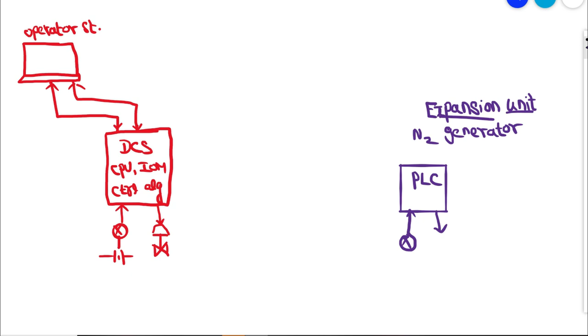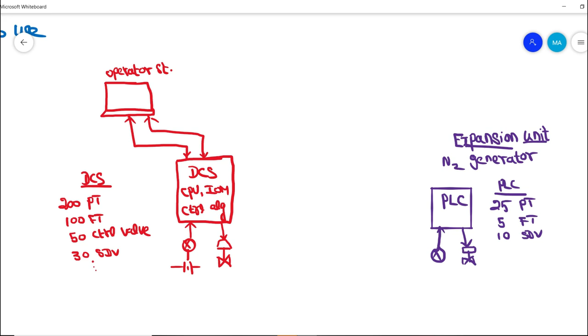Basically, in a DCS, we know that they handle more instruments, for example, 200 pressure transmitters, 100 flow transmitters, 50 control valves, 30 shutdown valves, etc. Similarly, in the PLC for this particular nitrogen generator, in an ideal condition, we are using 25 pressure transmitters, 5 flow transmitters, 10 shutdown valves, etc. So basically, the control room operator sitting in the control room would not have any data regarding the nitrogen generator unit which is added in the same process plant.